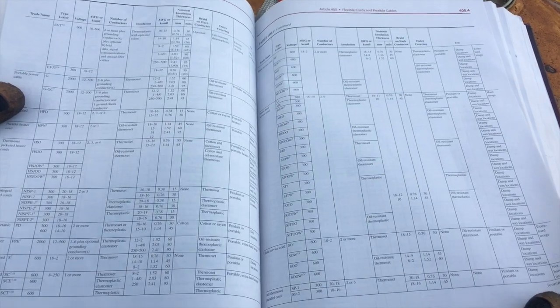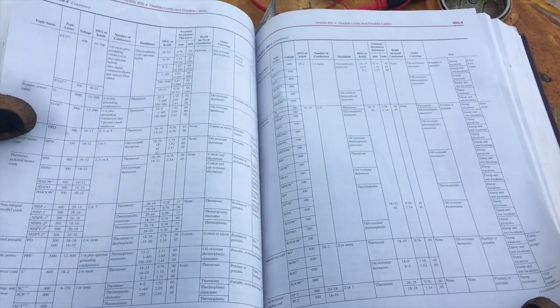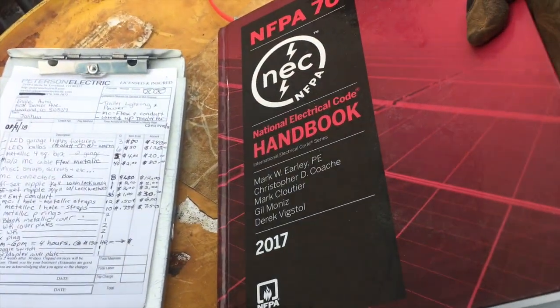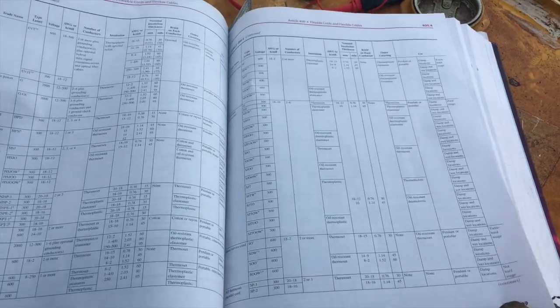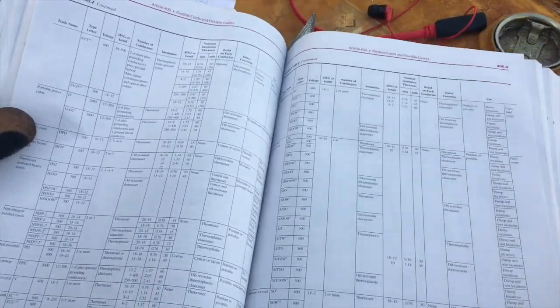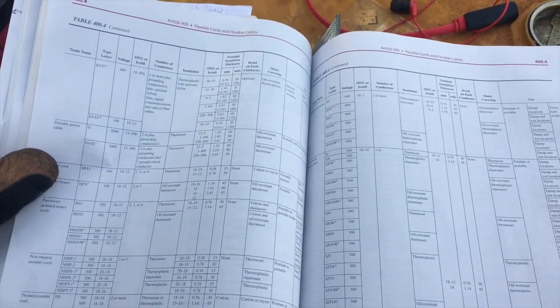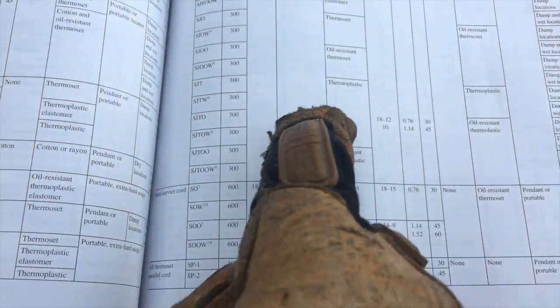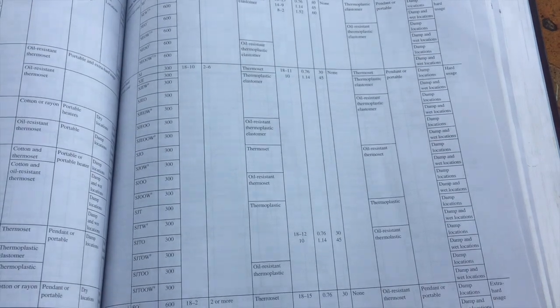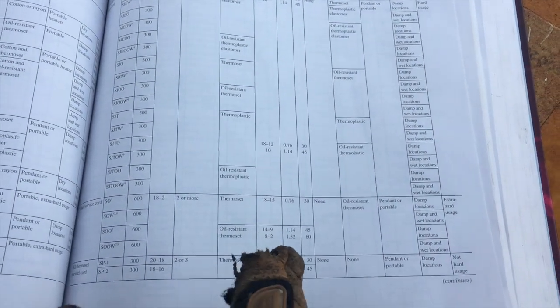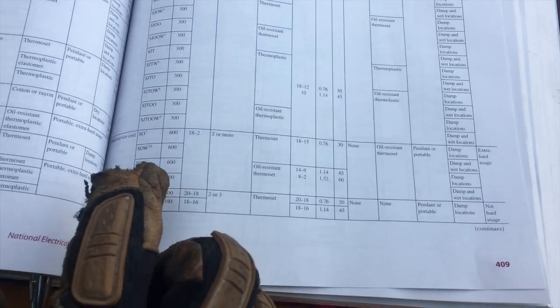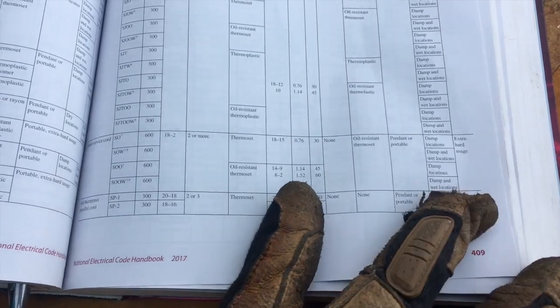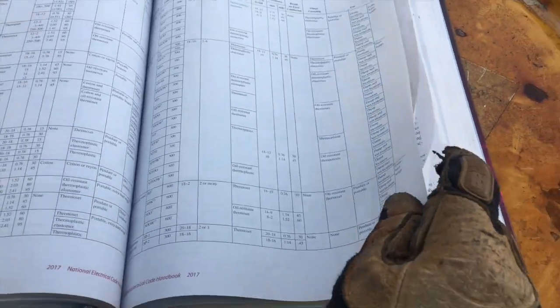You're also going to turn to, in here it's going to be, I've got a handbook by the way 2017, so that's page 409, but a JSOOW cord is going to state in here what it's rated for, if it's going to be oil, thermally rated, also wet, dry, damp, extra hard duty, things of that nature.